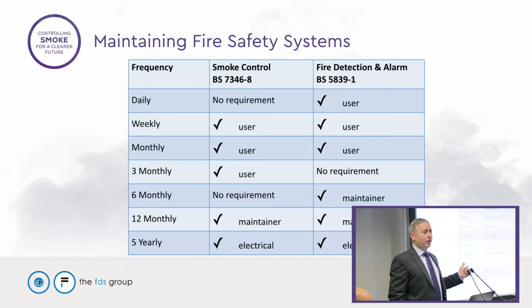Now, because there's no requirement under smoke control, I wouldn't advise not doing anything. I would also say check your smoke control panel. Make sure that also doesn't have alarms on. And I've been into some properties recently where there was an alarm on the panel, and it's probably been there for about 3 months. No one's recorded anything about it or passed it on. And I said, as soon as you tell us about it, we can do something. So these daily checks are your first line of defense in protecting your system.